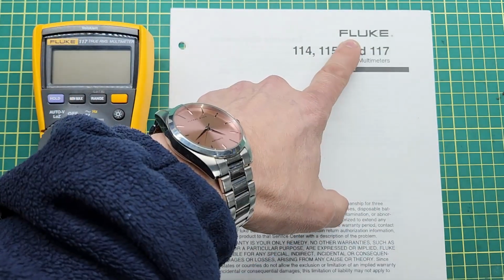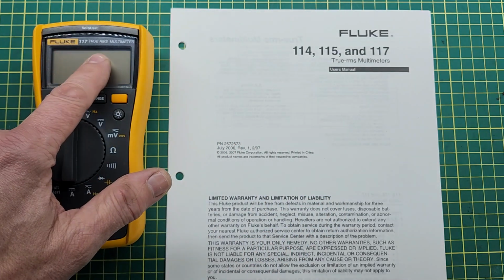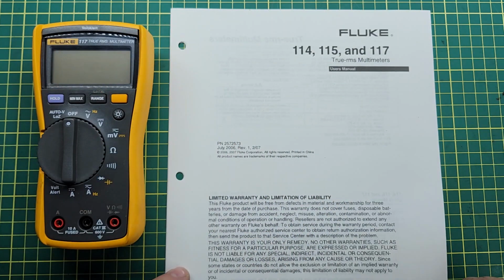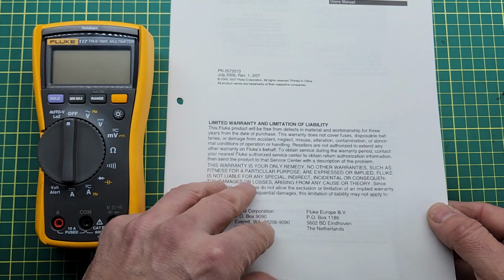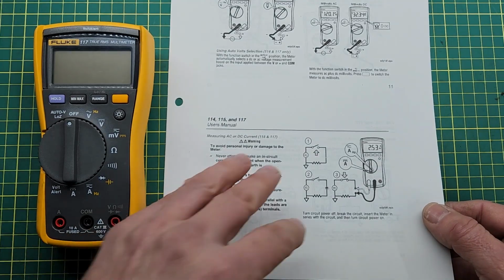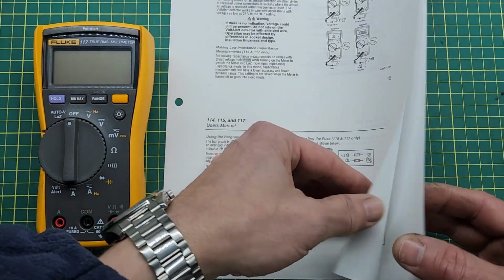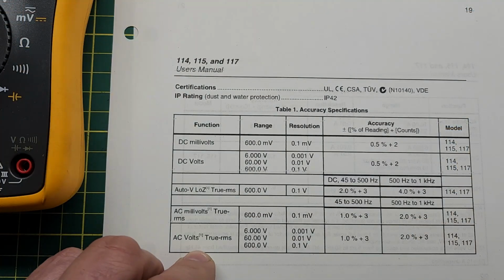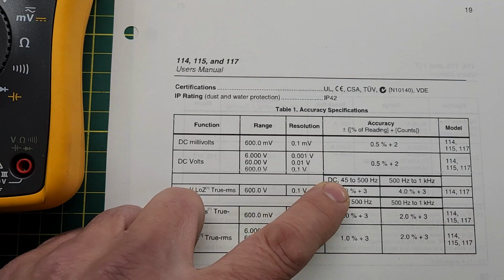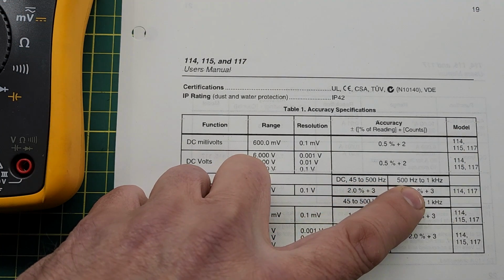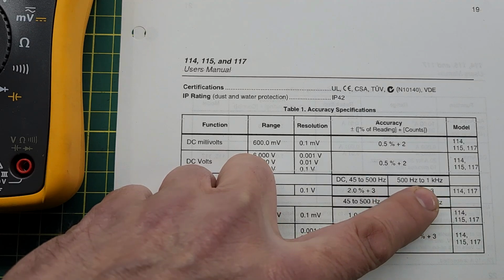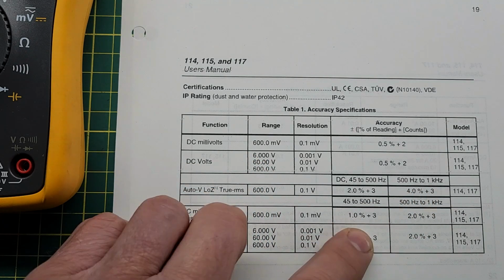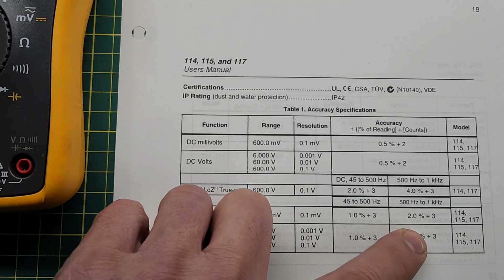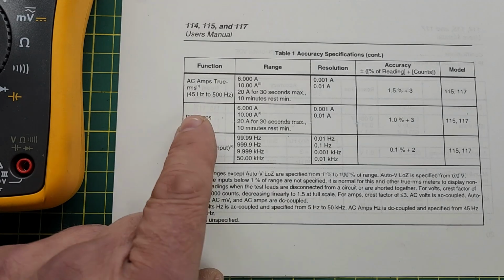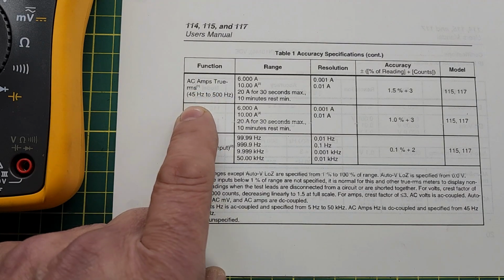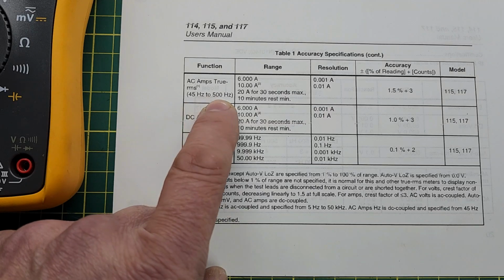Before using our device, we should know its limitations. For example, this digital multimeter handles up to 600 volts, but only within 45 to 1000 Hz frequency of an AC voltage, and its accuracy drops at a higher frequency. AC current measurement is even more limited, to only 45 to 500 Hz.